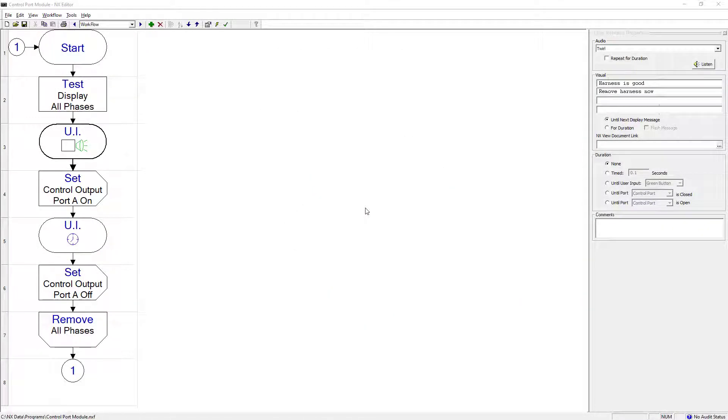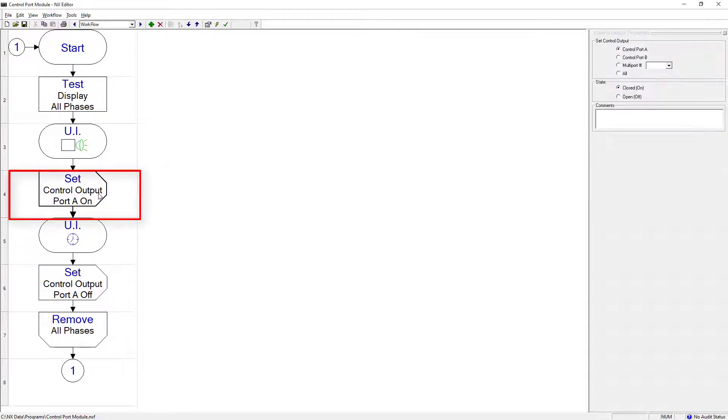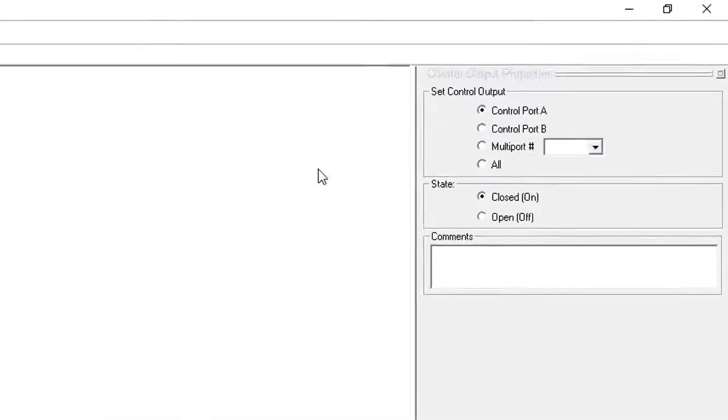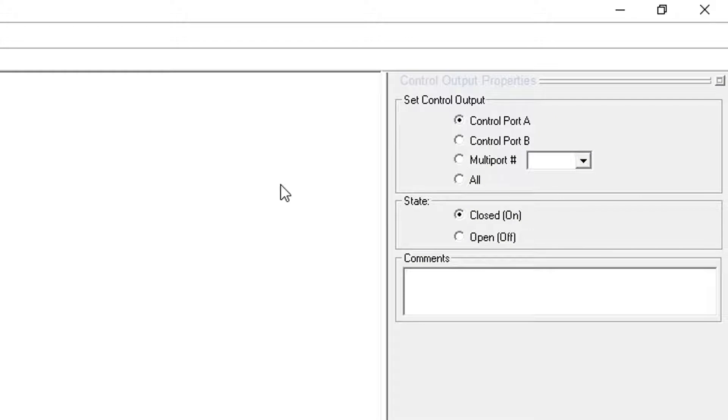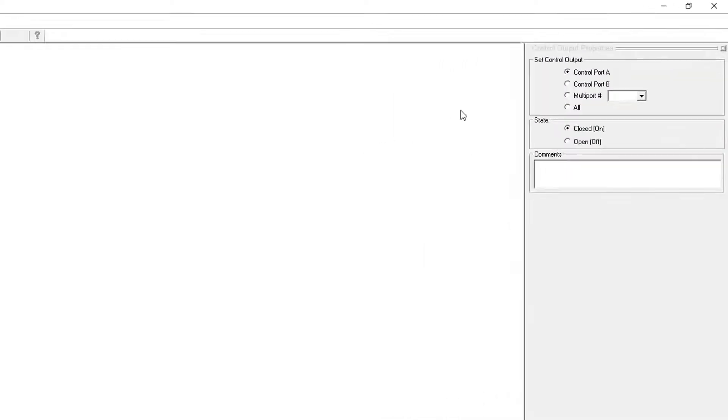Once the electrical test is completed, a set control output cell is used in step number 4. The relay A is activated in the control output properties. Then the circuit is closed and the external device receives the power.